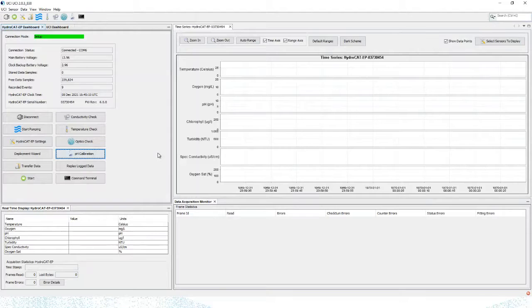That being said, you want to make sure you're doing it correctly and using fresh colorless buffer solutions while calibrating your pH sensor, to ensure that when you deploy your instrument out in the field, your pH sensor is properly calibrated, so that you can get that full 90-day deployment. It's going to get that 0.1 pH accuracy while it's out in the water. And you do it from within UCI. Now we can do things like a conductivity check, to check the conductivity sensor by putting a conductivity standard solution into the flow path. We can do a temperature check when this is installed in water, just to make sure that it's meeting the expected temperature and also remaining stable while it's deployed. And then you can run an optics check with the optics check cap that you can get with your HydroCAT EP.